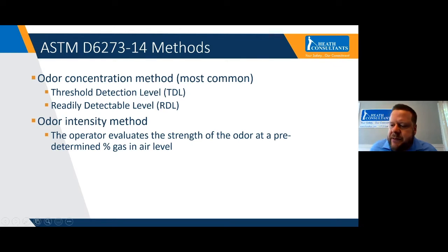So ASTM, which is the American Society of Testing and Materials, now known as ASTM International, has basically standards that recommend methods to provide odorant testing. And there are two different methods that are outlined in ASTM. The first one is the odor concentration method. And this is the most commonly used, at least in the United States, for odorant testing or sniff testing. This consists of recording two tests. One is a threshold detection level, and one is a readily detectable level. And we'll talk a little bit more detail on that as well. And then the second is an odor intensity method. Now, some utilities use both of these, some just use one or the other, but we'll go into detail on how each of these work.